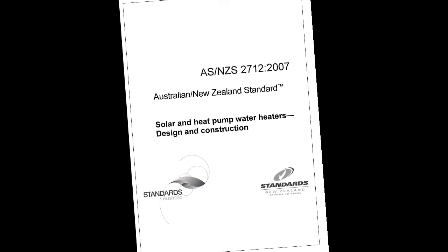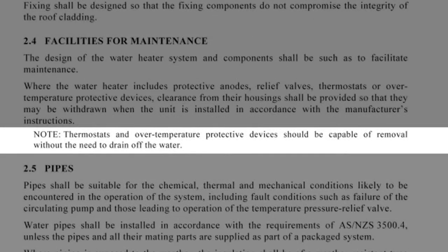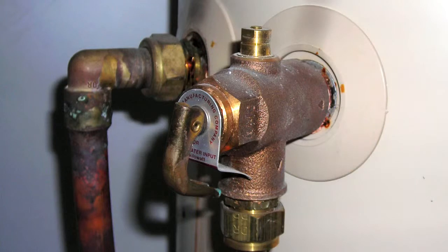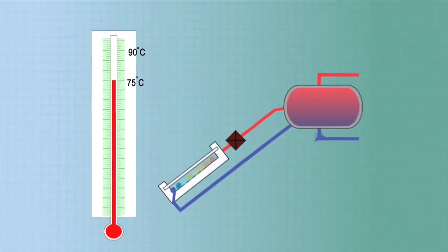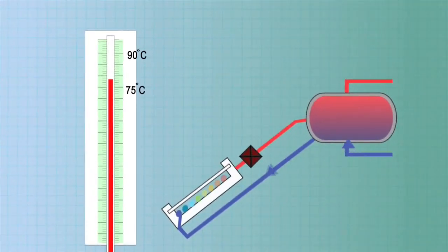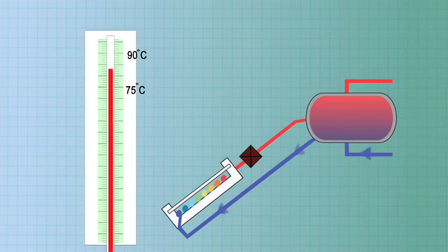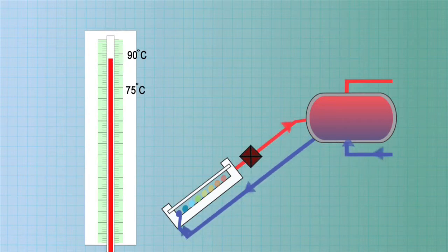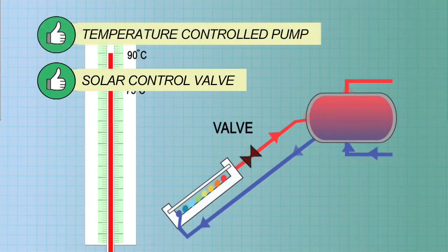The Australian standards state that solar hot water systems must provide over-temperature protection without draining water. So a temperature pressure relief valve is not enough. The most common way to prevent overheating in the tank is by automatically stopping the circulation between collector and tank when the tank water gets too hot. This can be done using a solar control valve or a temperature controlled pump.